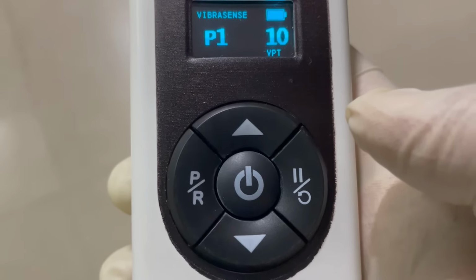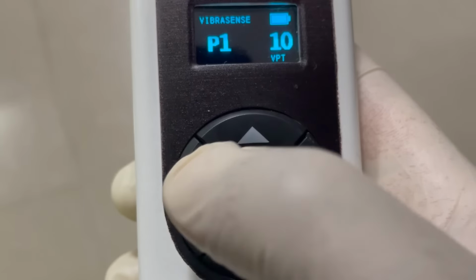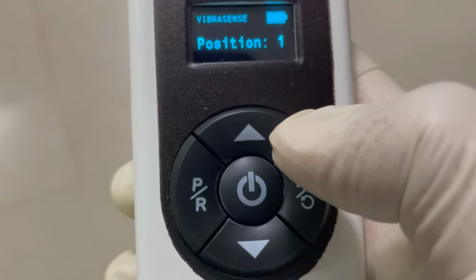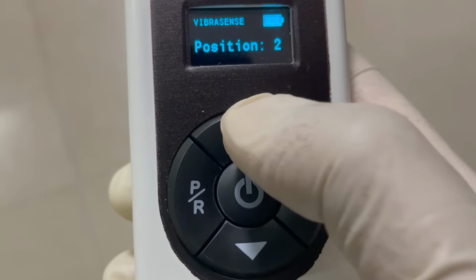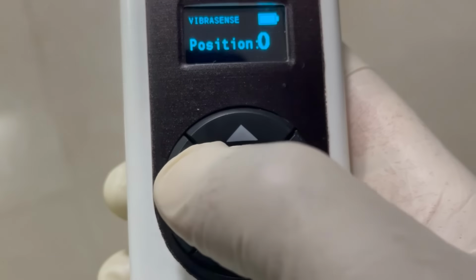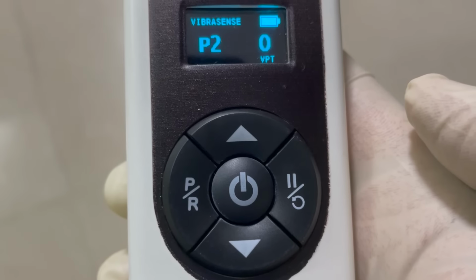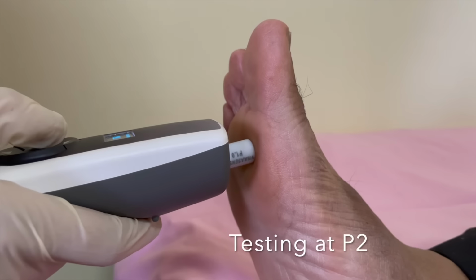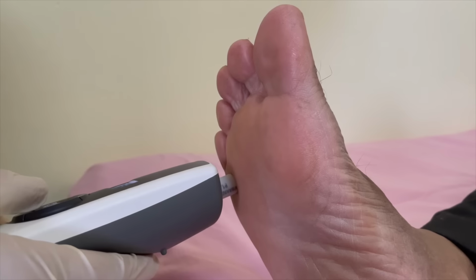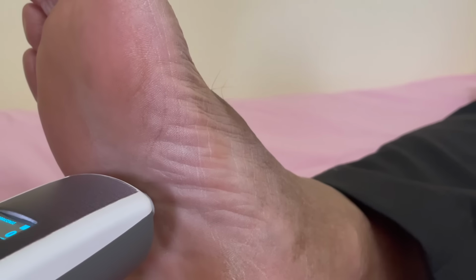Now press the PR button. This saves the last recorded data for P1 and brings up position 1 on the screen. Use the up arrow to select the next position, P2. Press PR again to freeze this position for testing. Now proceed to test at P2. Repeat these steps until you finish the testing at position 6 on that foot.